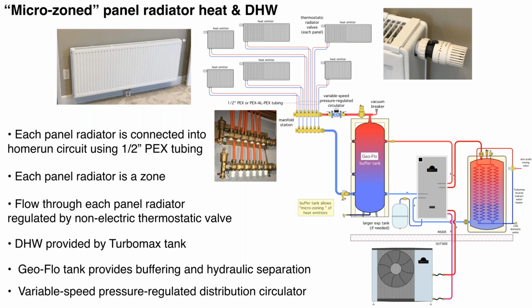I will stress, as we talked about in previous webinars, make sure you size these panel radiators for low water temperatures. I would suggest an average water temperature at design load of about 110 degrees. And that's well within the operating range of the heat pump. It's going to allow the heat pump to operate with good heating capacity as well as good COPs. Now, it does result in larger radiators. If you're thinking that you could heat a large master bedroom with a radiator 10 inches high and maybe 18 inches wide, you could do that with 200-degree water, but you cannot do that with a heat pump. So yes, the radiators are going to be larger when you go to lower water temperatures.